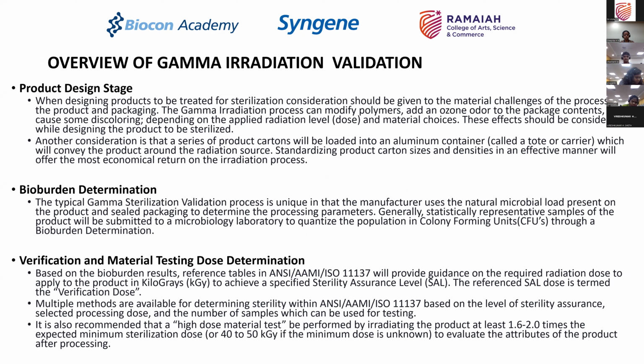What are the process steps involved? You have decided you want to do gamma irradiation, but if you want to do gamma irradiation, you need to follow certain steps. So these are the steps where you can validate the process more efficiently. First is the product design stage. When designing the products to be treated for sterilization, consideration should be given to the material challenges of the process on the product and packaging.